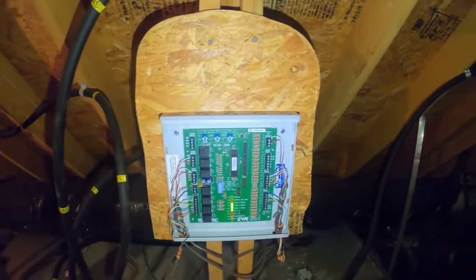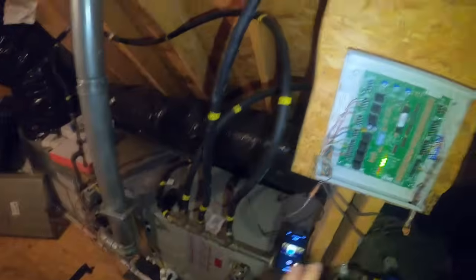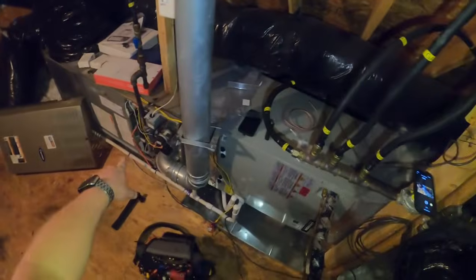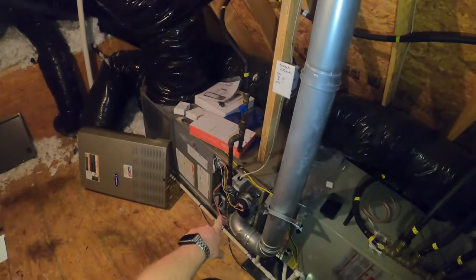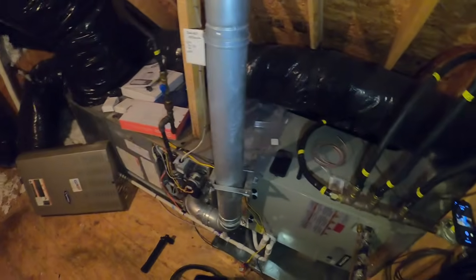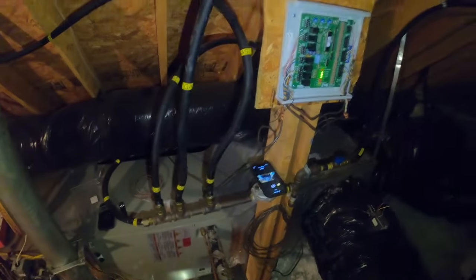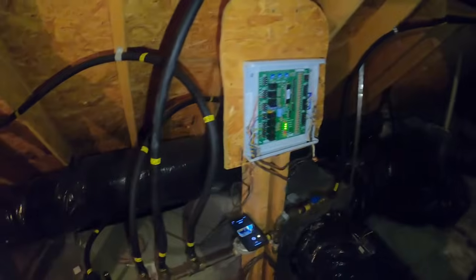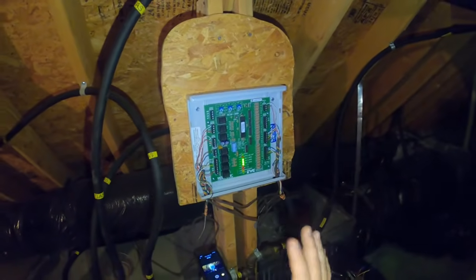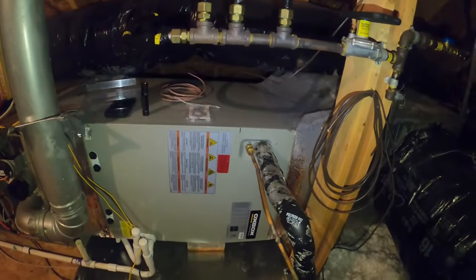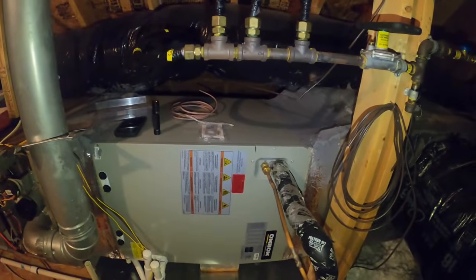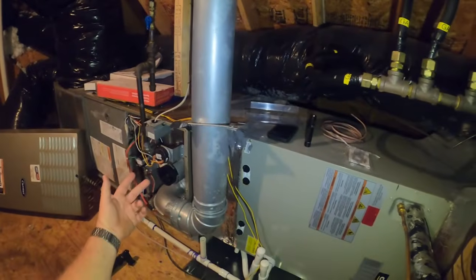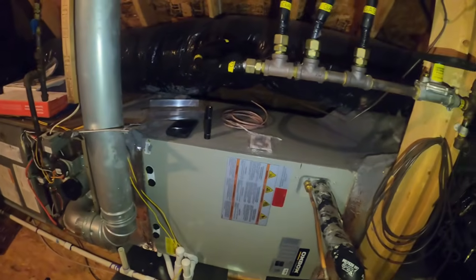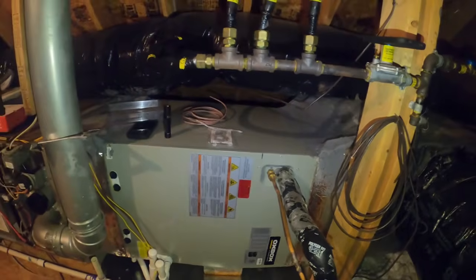All right, guys, we're up in the attic now, getting ready to swap out this Ultrazone EWC board. So we've got a single stage furnace over here, Carrier. We didn't get that replaced, but we did replace the air conditioner with an Oxbox heat pump, but we didn't put in a zone panel that could run dual fuel. This is a heat pump panel, but it doesn't allow me to specify on this particular panel whether we've got electric or gas backup heating, which means if it calls for auxiliary heating while the heat pump's on, this furnace is going to come on. It's going to blast that 120 degree air through this coil in heat mode, and your head pressures are just going to go bonkers.